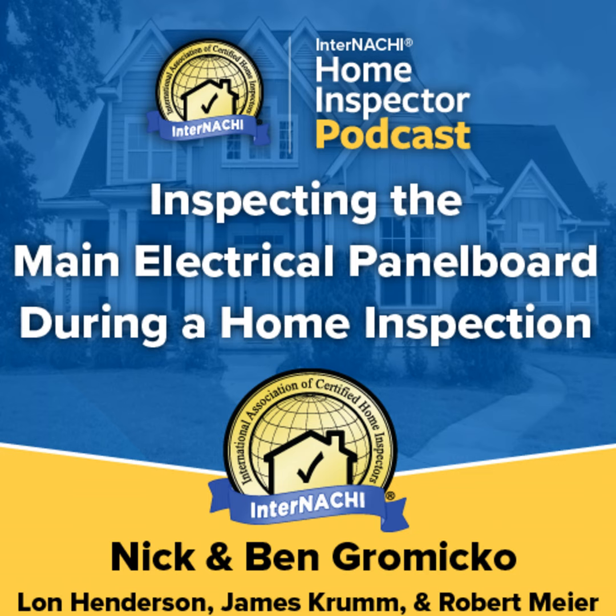The ungrounded conductors are typically referred to as the hot conductor, a current-carrying conductor. Grounding electrode. A grounding rod, footing reinforcing steel, and metal underground water pipes are examples of grounding electrodes, which are metal, electrically conductive terminals through which current enters the earth. There are several methods of connecting the grounding system to the ground, with a driven grounding rod being the most common in most areas. Most residential construction requires 2 separate grounding electrodes in any combination of the following, which need to be at least 6 feet apart.